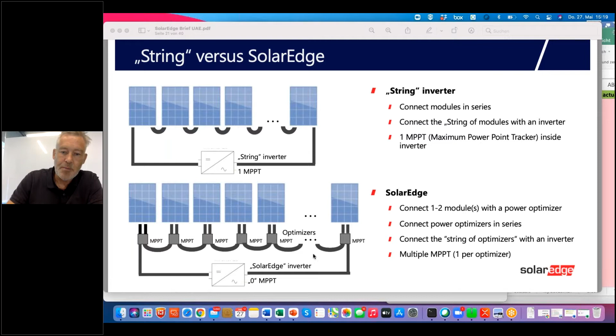But let me show you what this also affects. Let's take a typical 100 kilowatt system. Assume we are using 425 watt panels, meaning I am using 236 panels. Let's assume we take an 80 kilowatt inverter, so the DC-AC ratio is about 120%. A normal standard traditional string inverter might have, let's say, 6 MPP trackers sitting in the inverter.